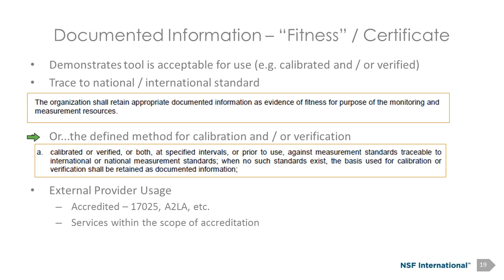The other section here, or defined methods for calibration or verification. Again, we need to have documented information when we don't have a national standard, we don't have that international standard. We're going to have some documented information that demonstrates its fitness for purpose against the method that we came up with. Okay? So not only do we need records of quote-unquote calibration, we need records to show our method for calibration. Now, if it's against a national or international standard, typically that certificate is going to say per procedure 123, per NIST number or requirement number. It's going to show somehow what that requirement was.